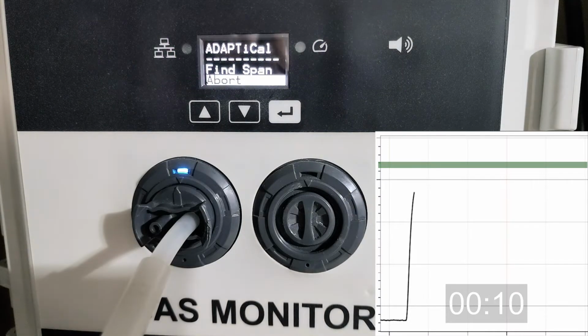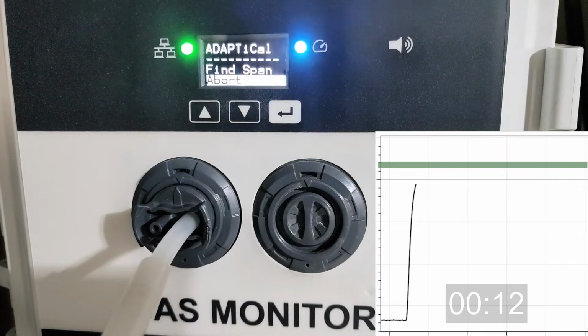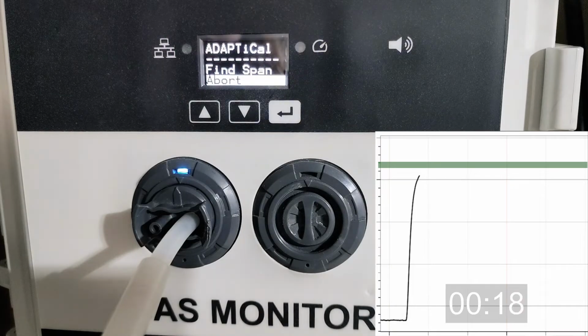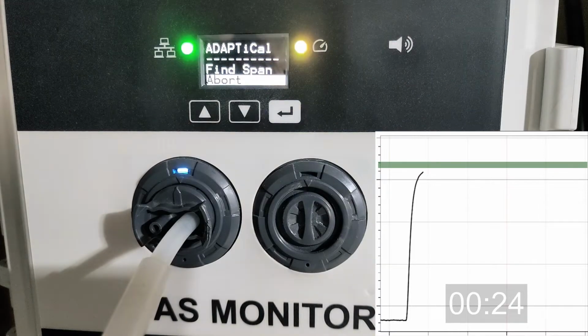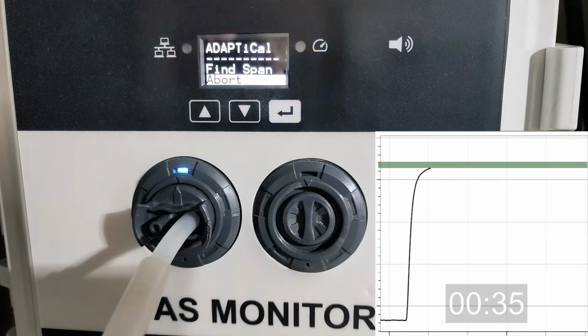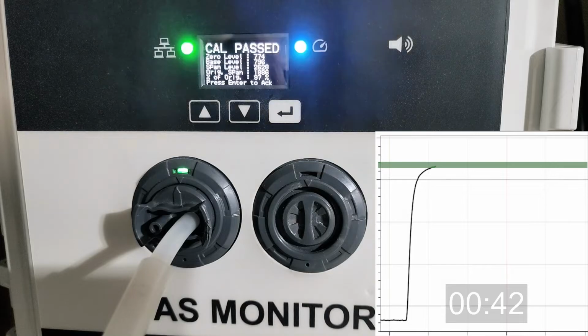During the find span stage, the self-referencing AdaptiCal algorithm is estimating a stabilization point of the sensor readings by identifying a stability region. In other words, the algorithm automatically establishes the point of calibration to the target gas based on the sensor signal variations. In addition, the method automatically adjusts the sensor reading to the ambient temperature using built-in temperature compensation. The algorithm was developed using data from years of in-lab testing. So here you can see that the calibration has passed and it's displaying the calibration results.